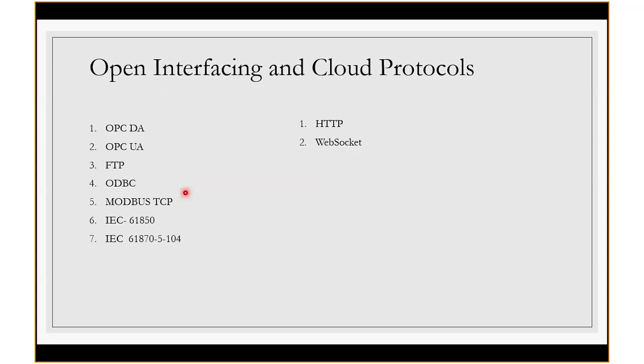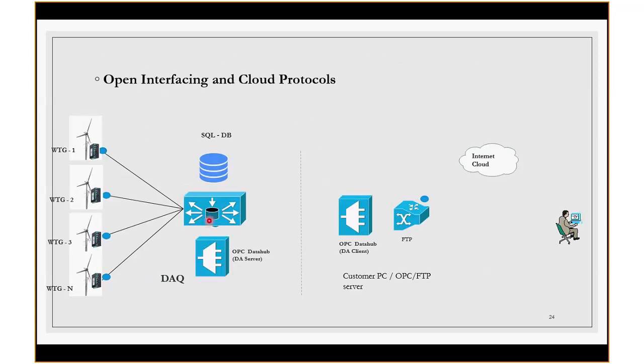So just to share this pictorially: here you may have Modbus communication, or IEC 61850 communication, or 104 communication. Once the DAQ fetches the data, it becomes available in the OPC DA server - this is the server and this is the client. The client fetches the data from the OPC server and does some computation to create a CSV file. Once the CSV file is created, it's pushed via FTP to the internet cloud. Once it reaches the cloud, it's a matter for the analytics engine - they build their models based on their experience and domain expertise.